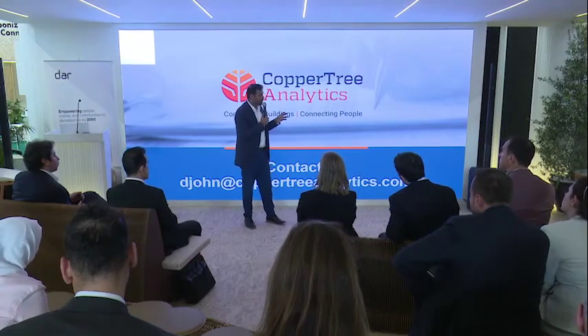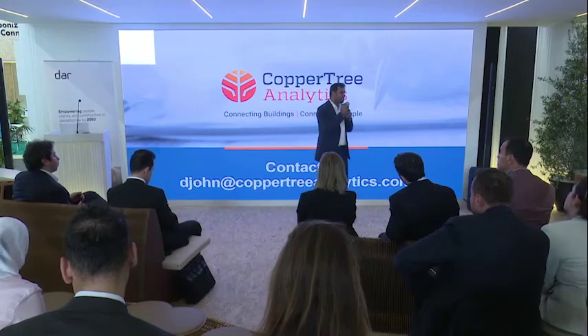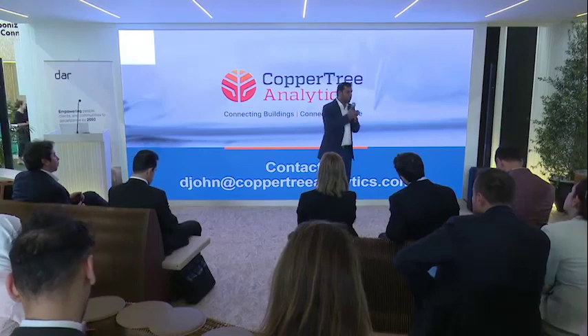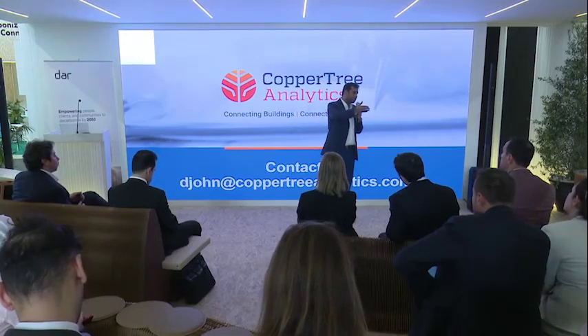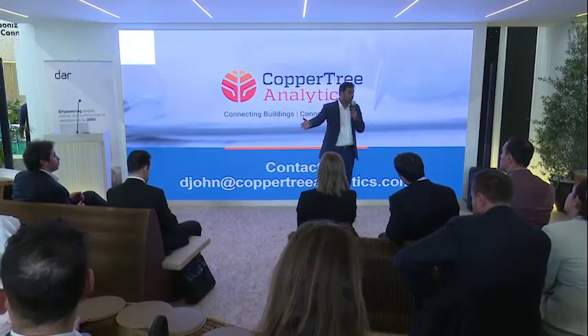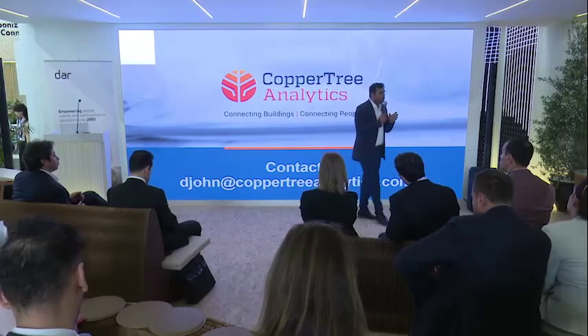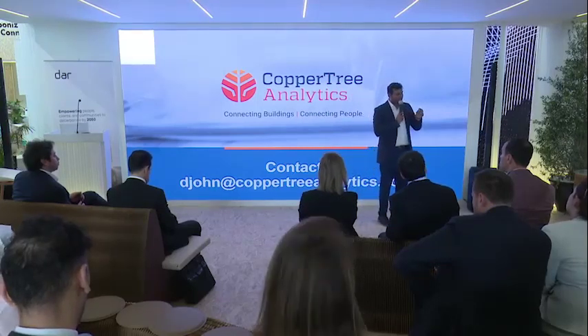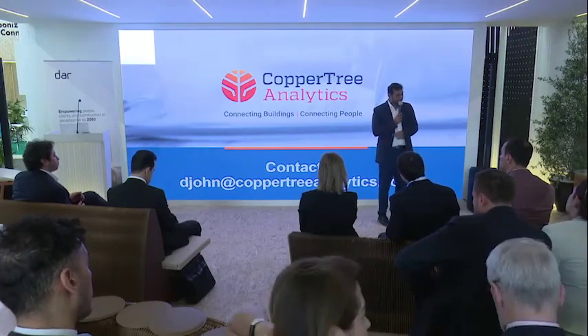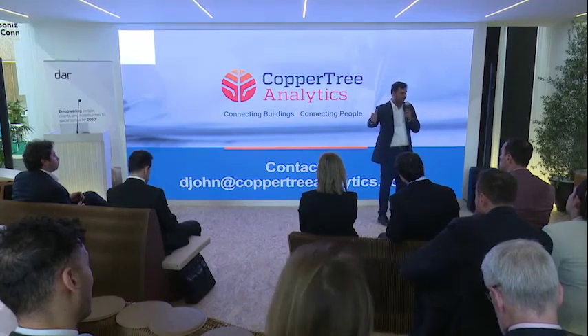The cool thing is, at any given time with an analytics platform, let's say you made an assumption that was inaccurate. It could happen in the real world. You thought that this particular system is supposed to be feeding 50 VAVs, but it's only feeding 30 VAVs. It's a change, right? It's not something that you anticipated in the beginning. What you can do with an analytics platform is make the change in the rule 16 days, 16 months after the fact. With the click of a button, it'll go back and rewrite all of the calculations, right?